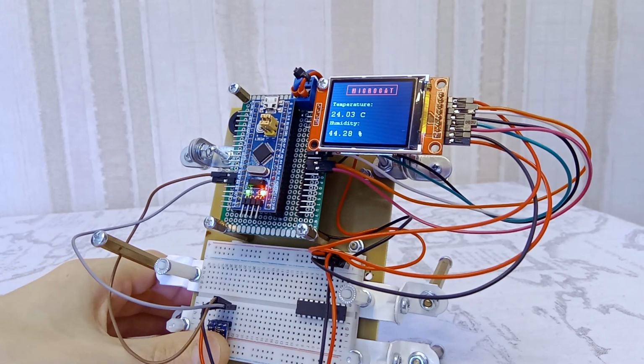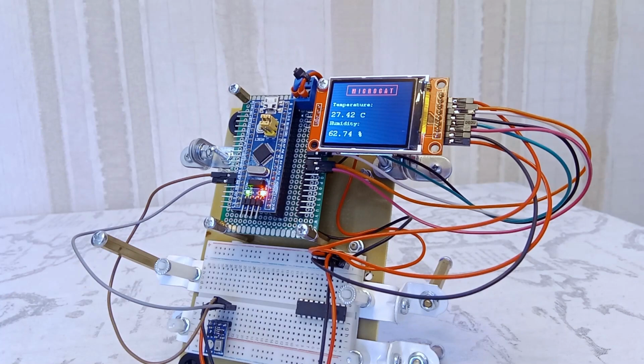Let's try a primitive test, namely you can touch the sensor body. In this case, the temperature rises rather slowly, in contrast to humidity. This is due to the inertia of the housing and the fact that the sensing element is inside. At the same time, the humidity changes faster, since the molecules of moist air very quickly reach the sensor. After releasing the finger, the situation is similar. Temperature drops more slowly than humidity.